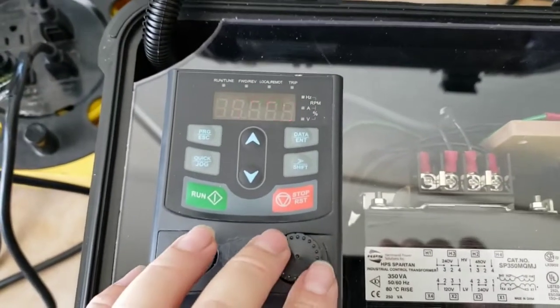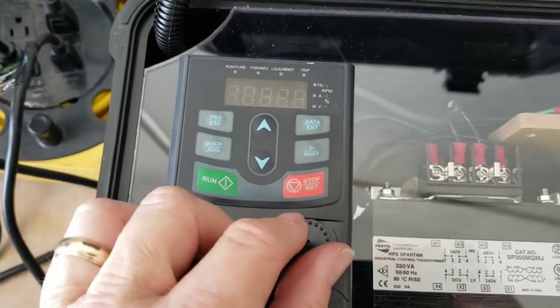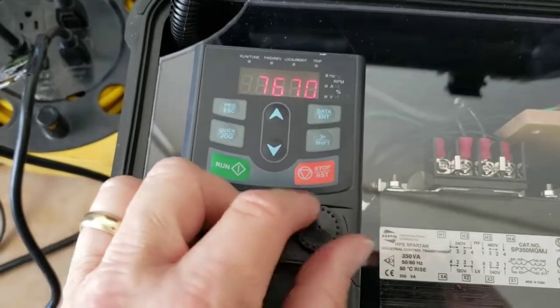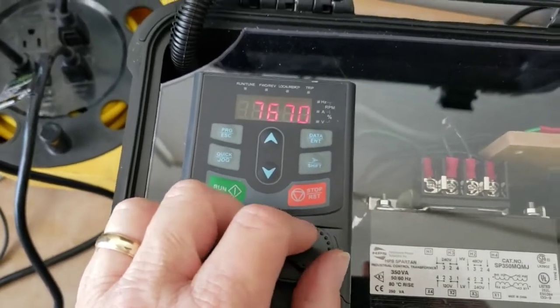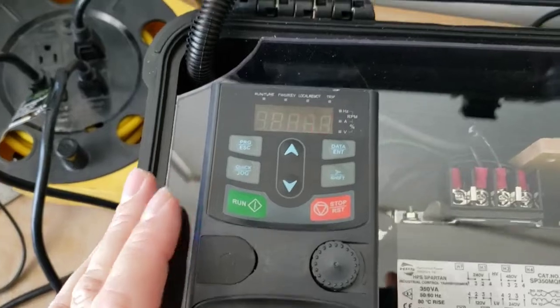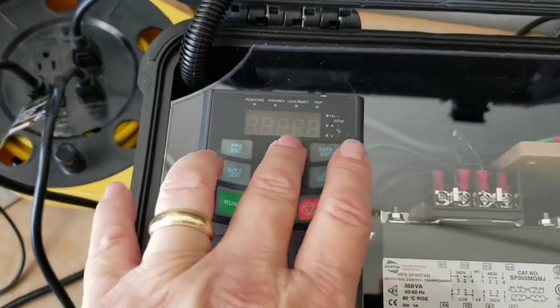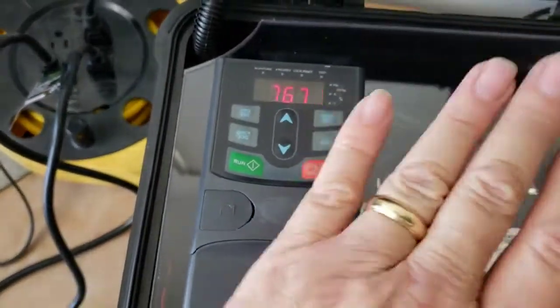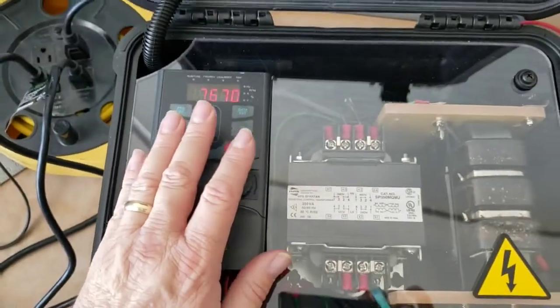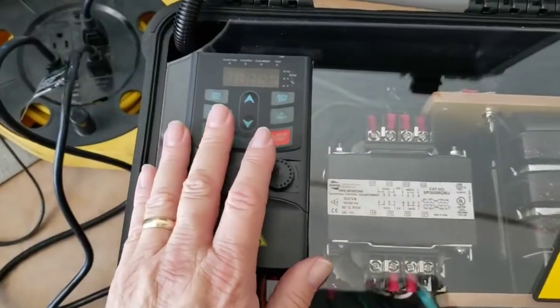So that's the most common way, is just to turn it on, slowly ramp it up from 0 to full power on this potentiometer. If you're getting up into around 400 watts, generally that means the cell's okay. And with this particular box, the frequencies may change as we make modifications to the high voltage transformers over time.